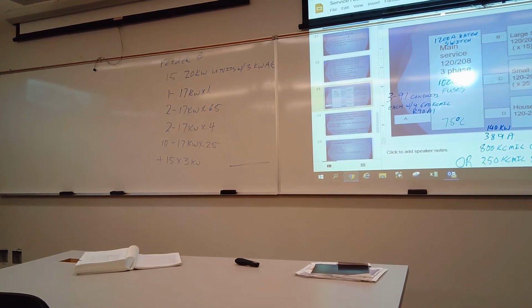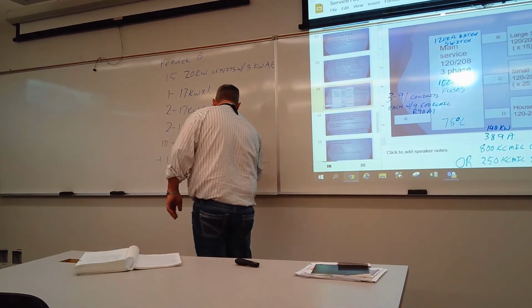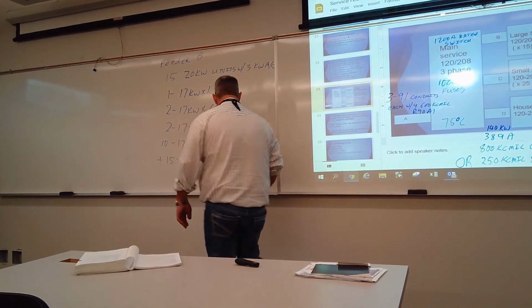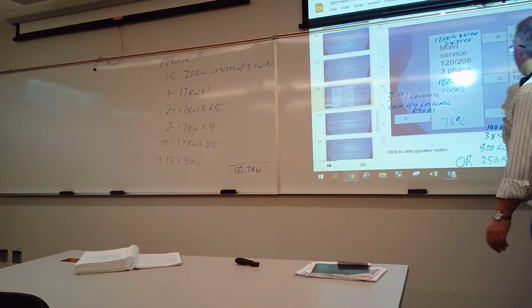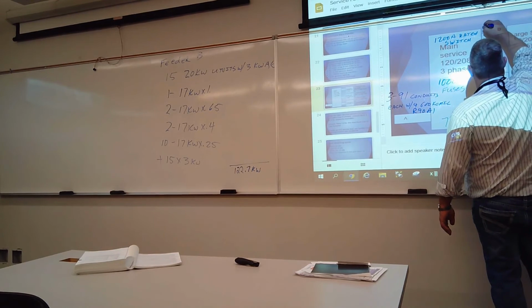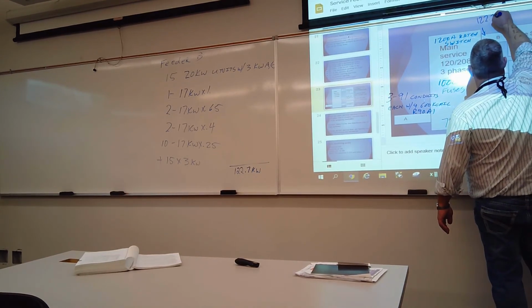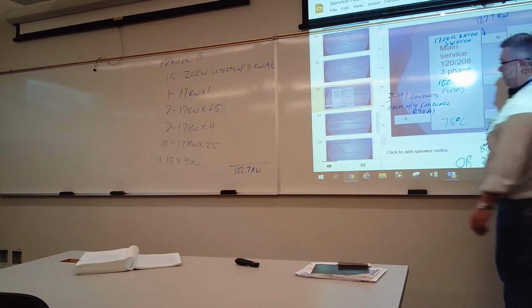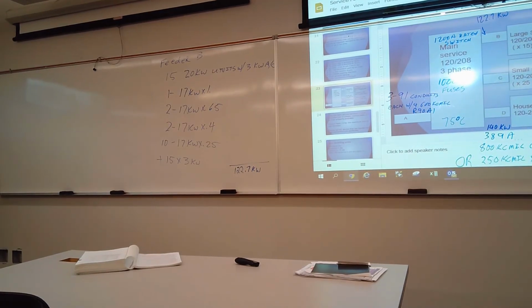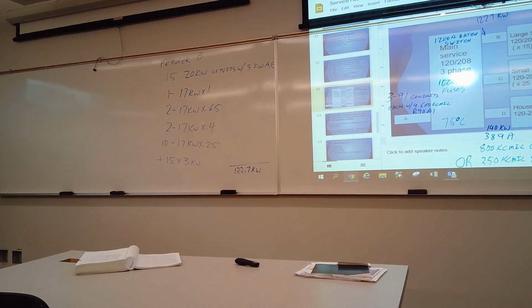122.7. Divided by 208 times root 3 gives us an ampacity of 341.